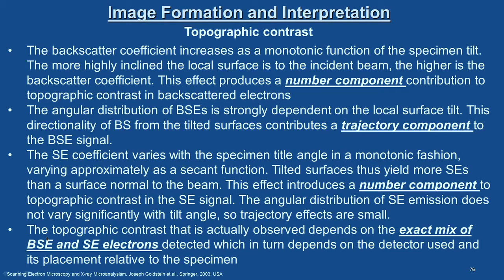The topographic contrast actually observed depends on the exact mix of BSE and SE electrons detected, which in turn depends on the detector used and its placement relative to the specimen. The final detector configuration — where it is placed with respect to the specimen and the electron beam — is very crucial in detecting the signal and its contrast.